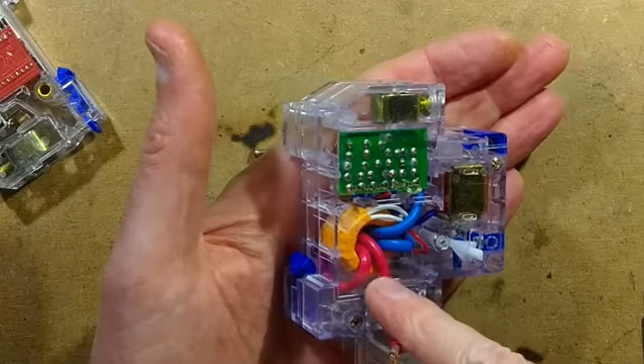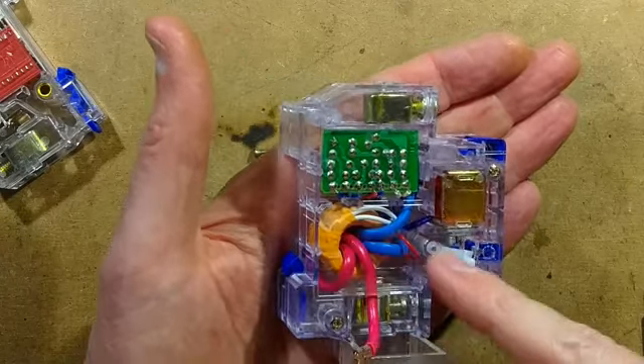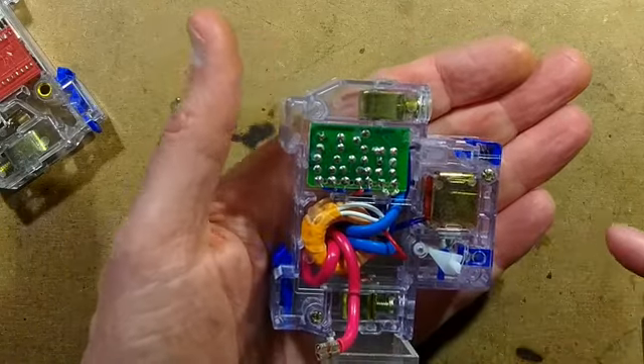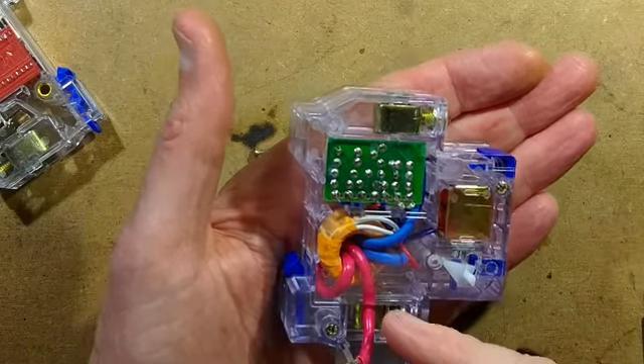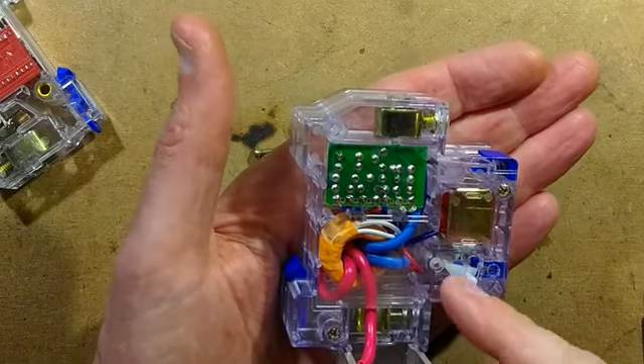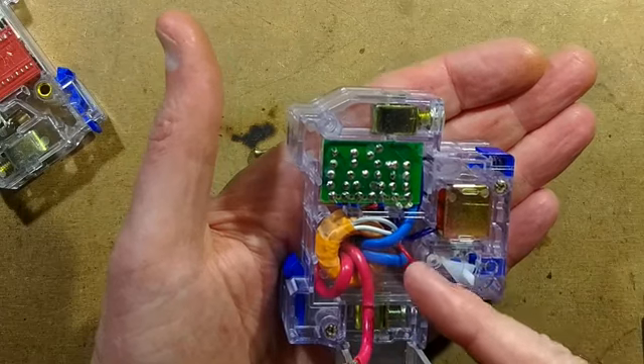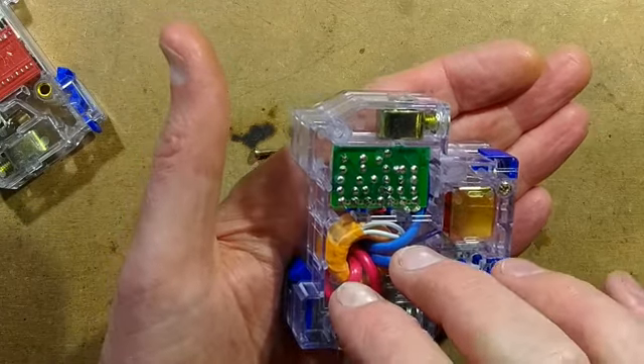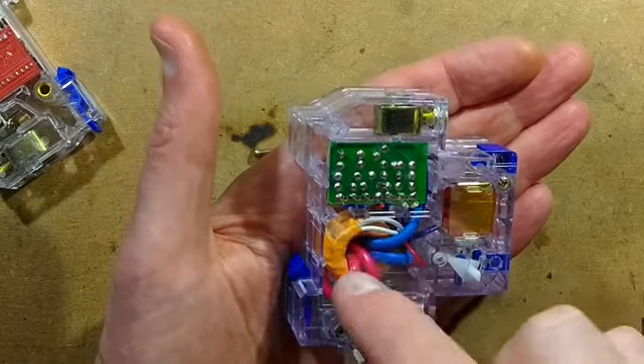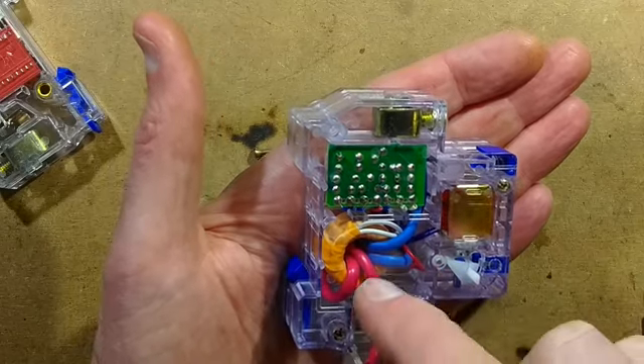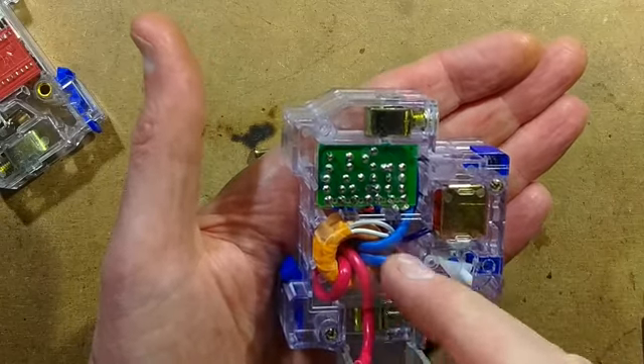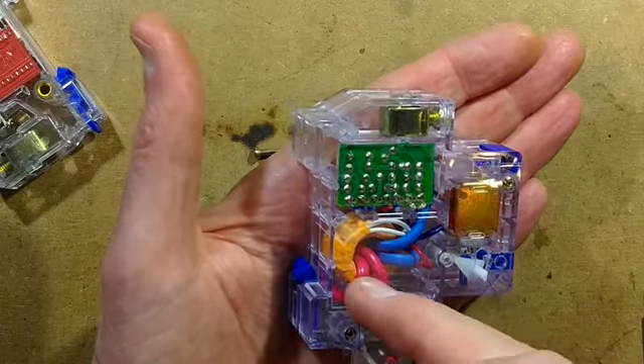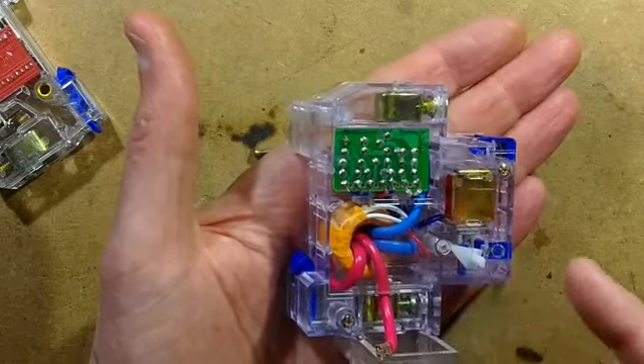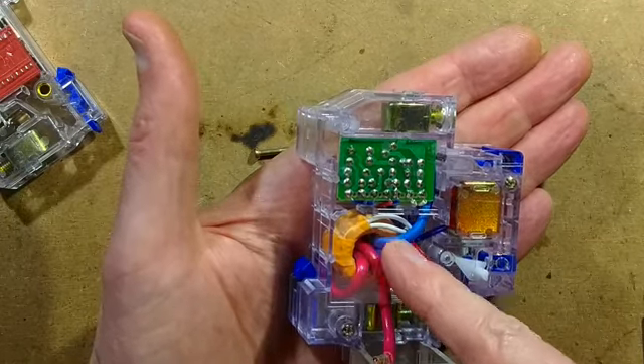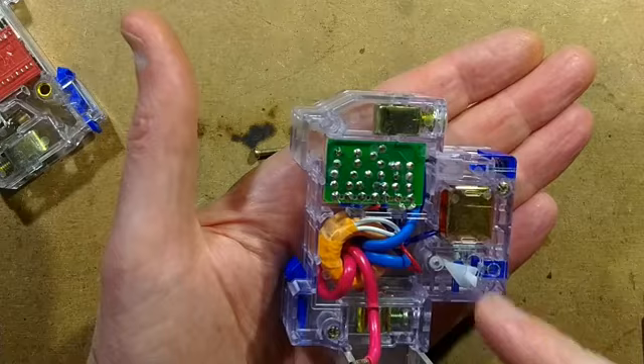It's got windings going through this toroidal core, and the current is effectively flowing out through the blue and then back through the red, or vice versa. Each of them is wound in such a way that if the currents are equal, the load is normal, it will cancel any magnetic field out in the toroidal transformer. If there's an imbalance, it will induce magnetic flux in the toroidal transformer, which is picked up by this little sense coil with the 2 white wires here, and triggers the mechanism.